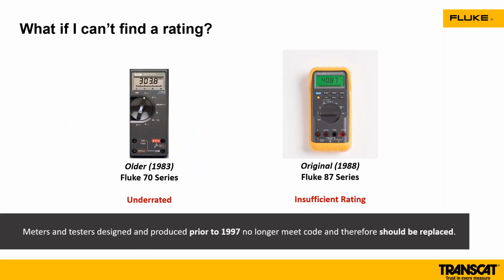Now this slide's great because, with a lot of the older meters, and I go to trade shows, I hear stories like, hey, I'm using the original meter my dad used. My grandfather gave me this meter and it's been great and it still works great. But just know that these meters are unrated, underrated, or insufficient. That older meter back in 1983, that Fluke 70 series, I know people still have this Fluke meter. It's actually not rated for those larger category environments. It wasn't there at that time.